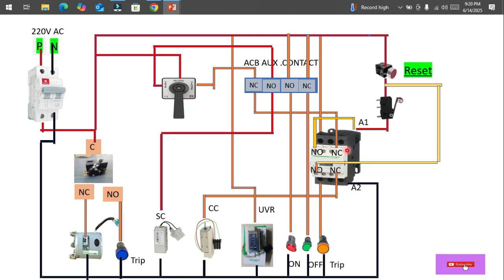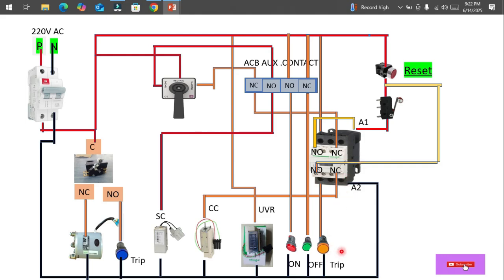This is a holding circuit. If due to any fault the ACB goes into trip mode, and we still try to close the circuit, the trip contactor remains activated and its NC contact becomes NO. This means if someone tries to forcefully or mistakenly close the breaker while there is still a trip fault, the contactor will not allow the closing coil to activate — it acts as an interlock.